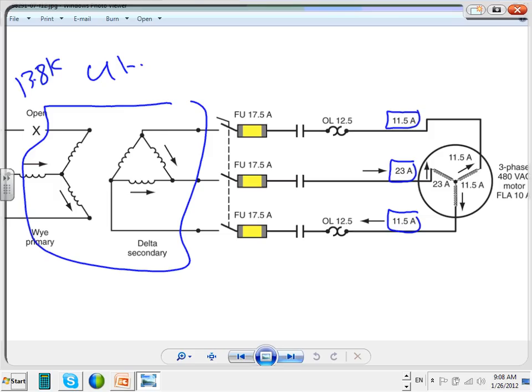Who cares? Then if you overload, if you don't have an overload protection here, what's going to happen to this coil right here? What's going to happen to this coil that's rated for 10 amps, and now it's carrying 23 amps? It's going to burn. But if you put an overload of 12.5 here, and you're pulling 23, what's going to happen to the overload? It's going to open. So anyway, all these examples hopefully will help you understand why an overload is very important for motors, in a Y or in a delta, on the primary transformer or secondary transformer.